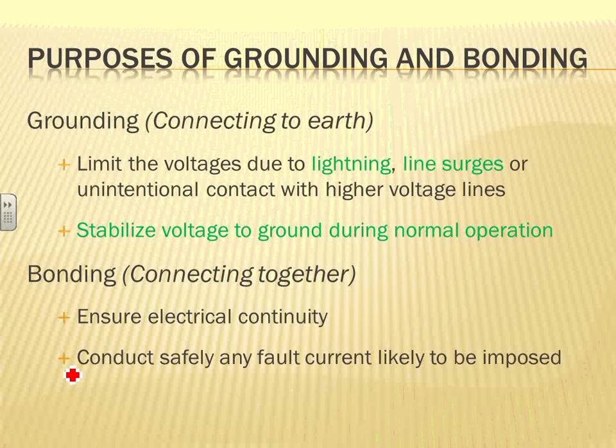If you have a ground fault in this fixture right now, it will trip the branch, hopefully just the branch circuit feeding it. So if you have a ground fault in the air handling unit, that one ground fault will trip the whole air handling unit. So that's the disadvantage. Advantages of an ungrounded system, guys, is the assembly line.